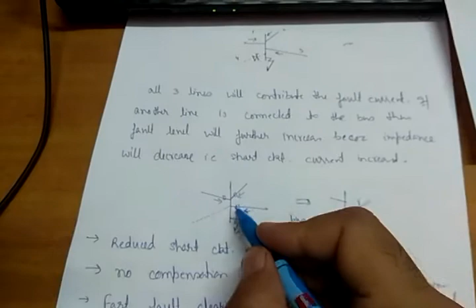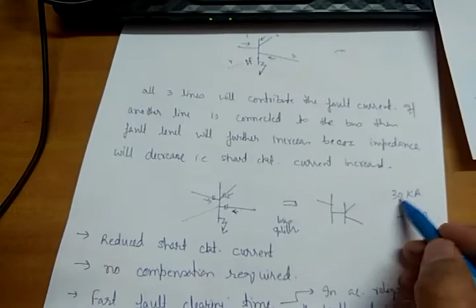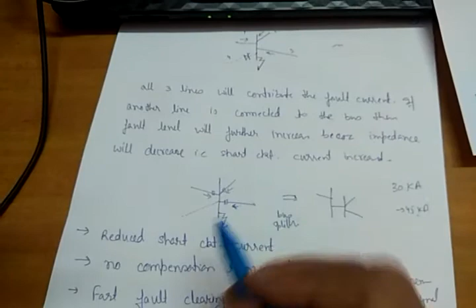In case I am using circuit breakers here, here and here, these circuit breakers have a capacity to break a maximum rated current. Suppose 30 kilo ampere is the maximum rating. Now I connect two or three more lines to this bus. The short circuit current may go beyond 30 kilo ampere, maybe 45 kilo ampere. These circuit breakers can break 30 kilo ampere, but the current is now 45 kilo ampere, so they may not be able to break this current and may get damaged.